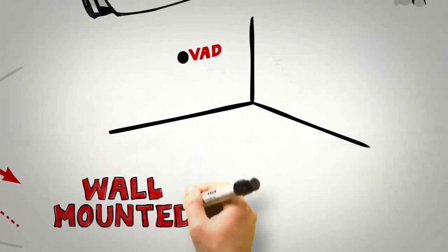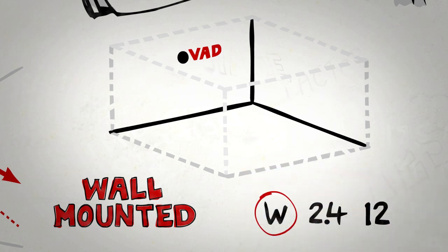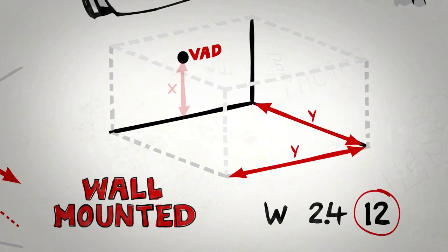The light level from a wall-mounted VAD is measured in a cube shape. The performance of this device is presented in a code like this one, where W stands for the wall category. 2.4 is the height that the device should be mounted at on the wall, and 12 tells us that it will cover an area of 12 meters by 12 meters.